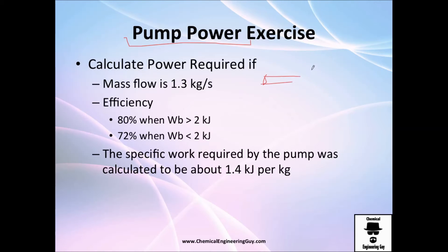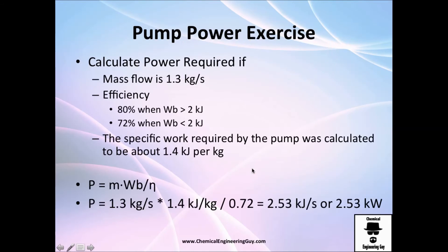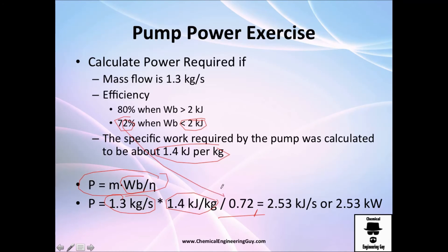Let's do an exercise on pump requirements. We have a pipeline with a pump, a given mass flow, and two efficiency values: we use one efficiency when the requirement is more than 2 kJ/kg, and another when it's less. The head requirement is 1.4 kJ/kg. So: mass flow is 1.3 kg/s, system head is 1.4 kJ/kg, and since the requirement is less than 2 kJ/kg, we use an efficiency of 0.72.